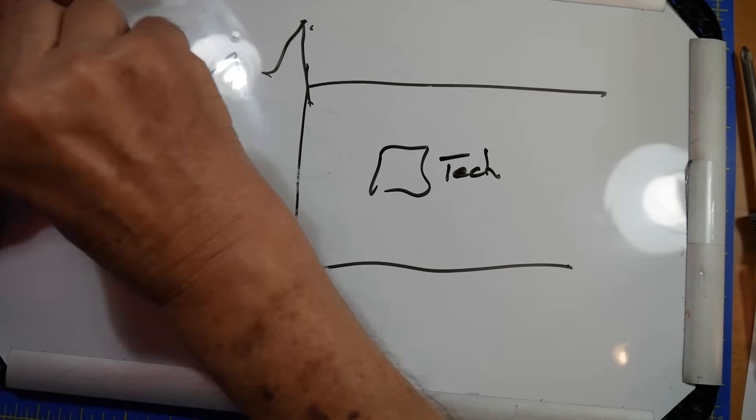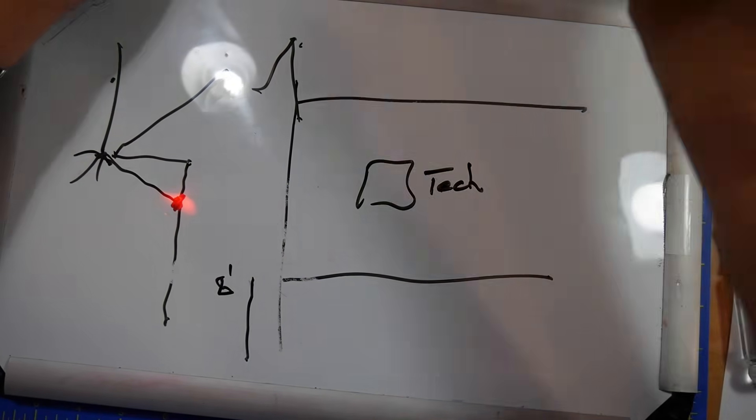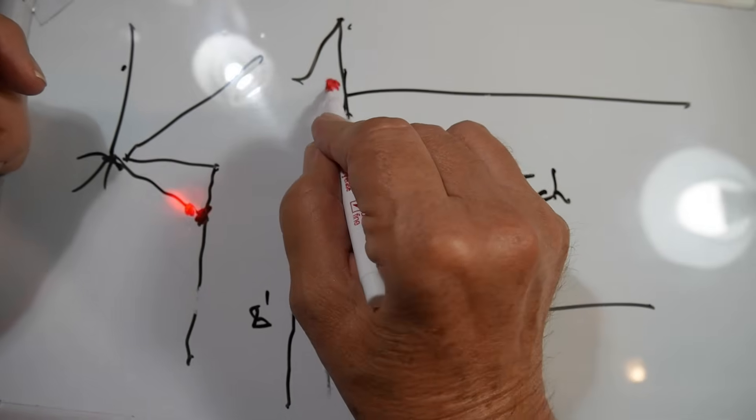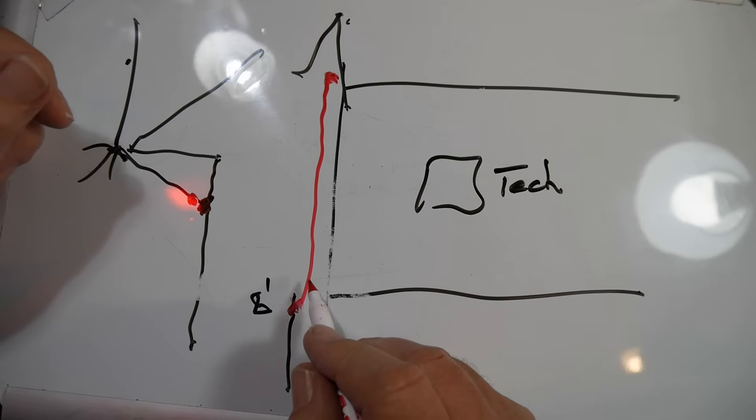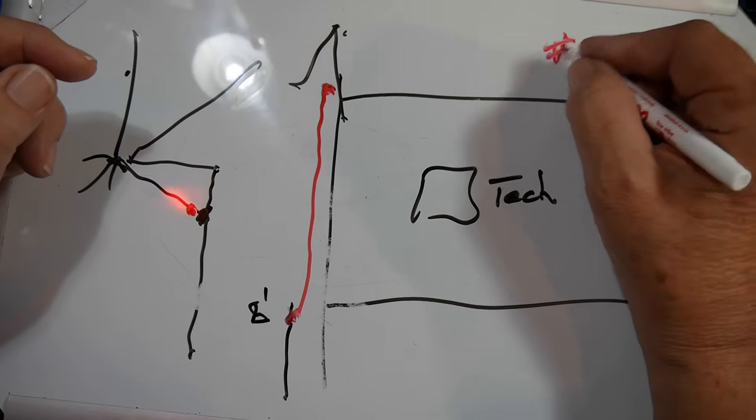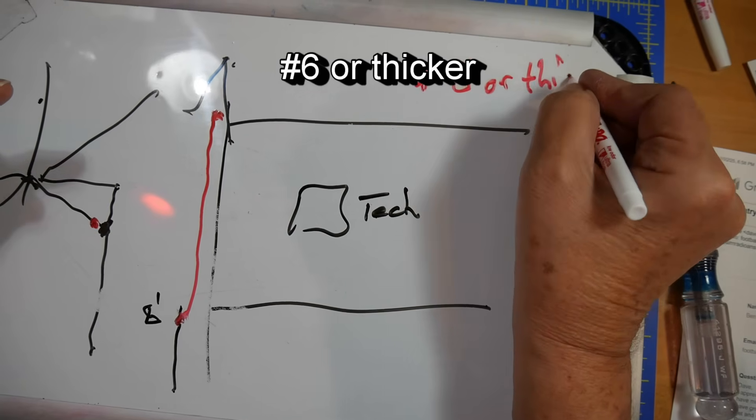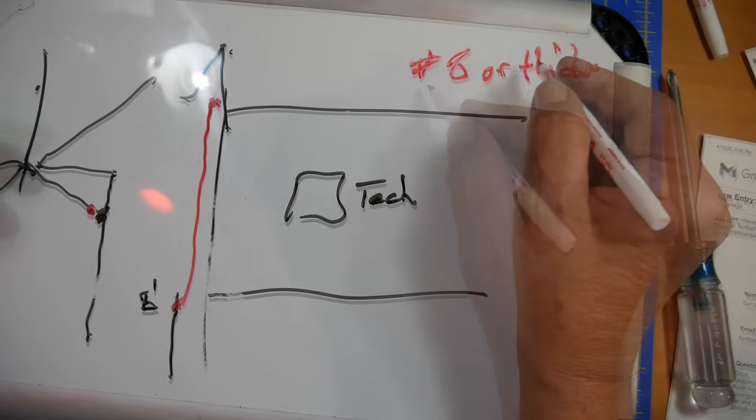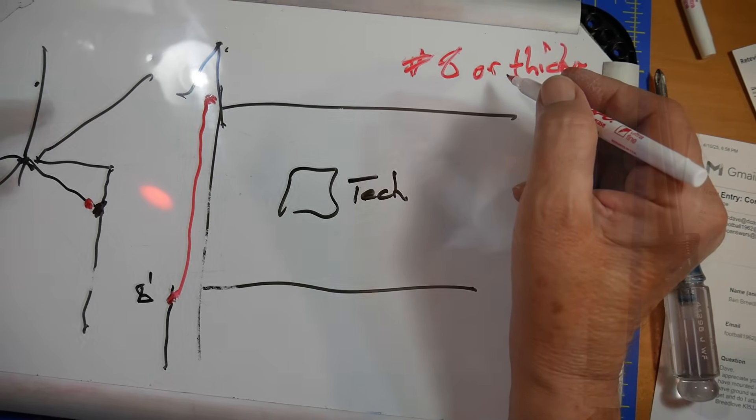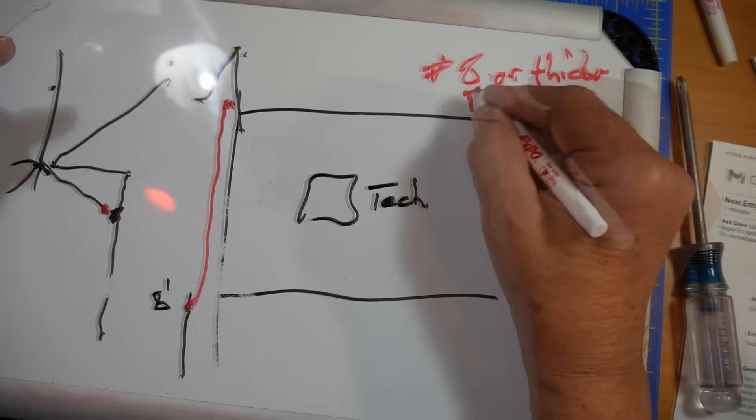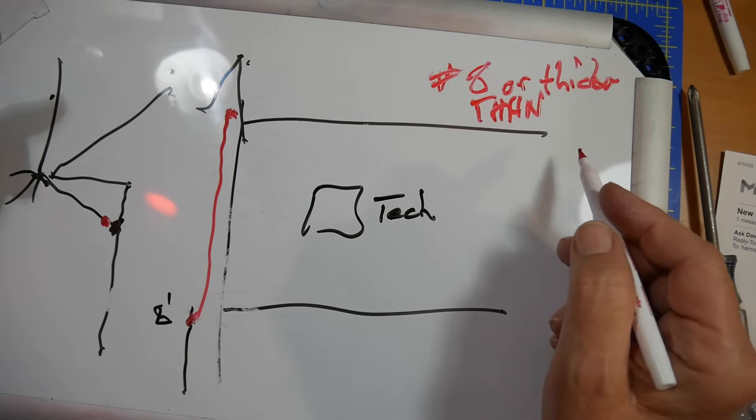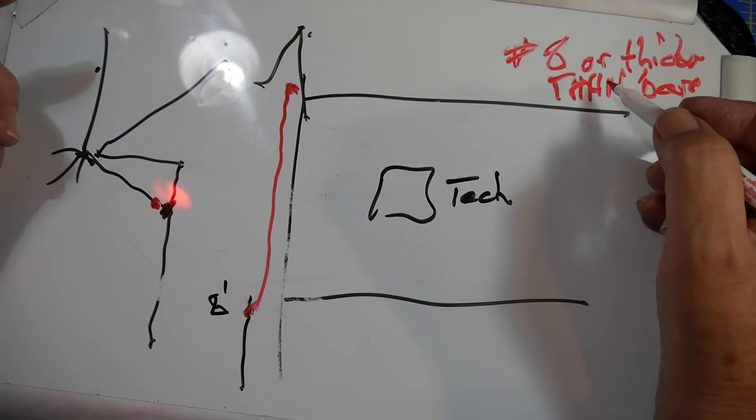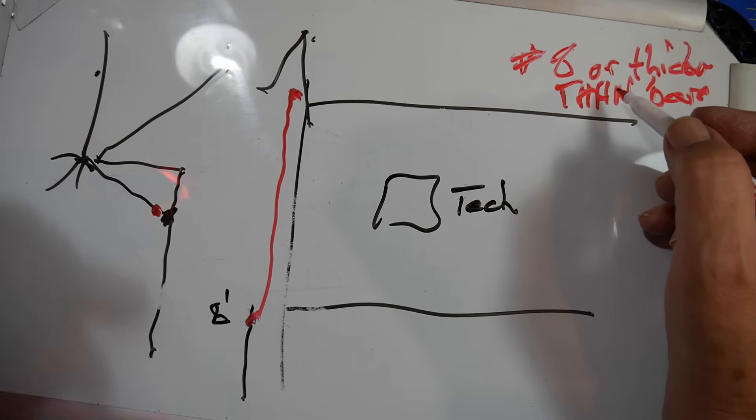Okay, two things really. And I'm going to go with what would be good and what would be better. This pole right here, which is right here, can come down to the eight foot ground rod with the crimp connection on here. And technically, this should be number eight or thicker. Now, of course, the way they do American wiring gauge, a number eight is thicker than a number ten is thicker than a number twelve. You can get it insulated or not insulated. I would recommend probably insulated for the stretch right here. Just plain old THHN. You can get this easily from Home Depot or you can go bare. Okay, so that is the recommended. Now, does it terribly matter?